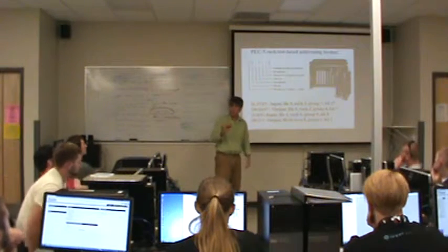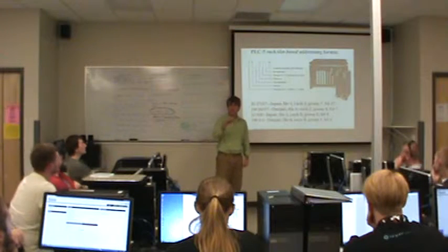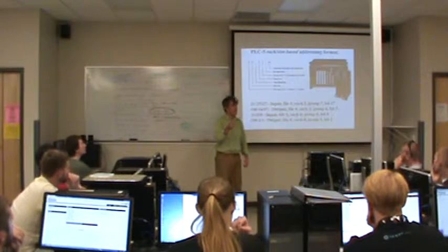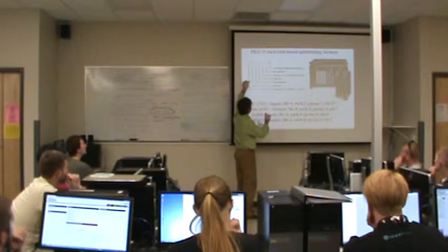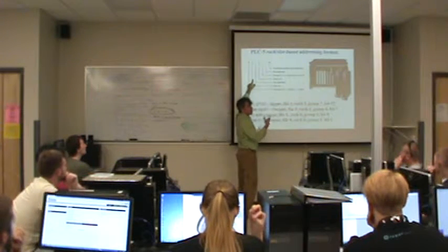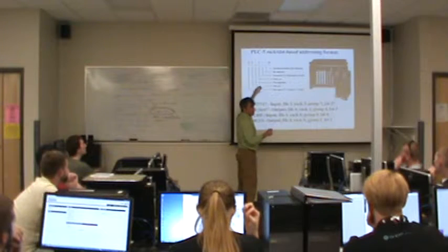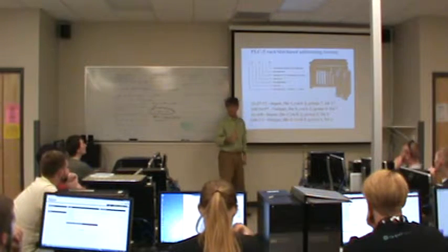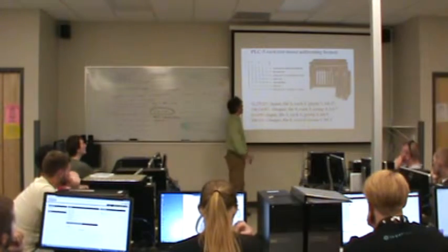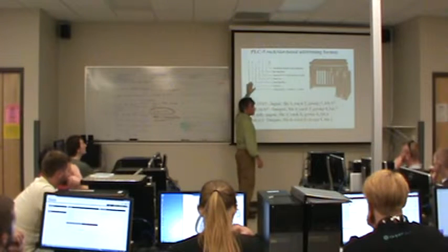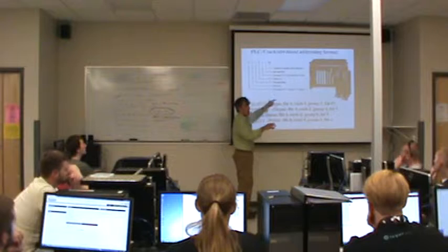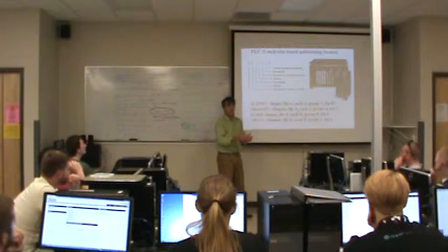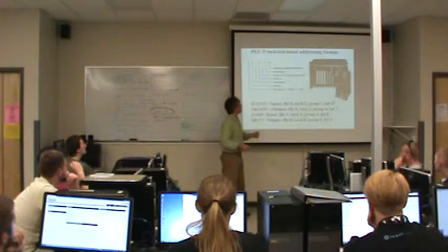Now, when that changes is if you define a file above file 9 as being an input or an output file, then you would need to say I, and then whatever the file number is. For example, I10, you could make an input file, or I11 could be an input file. You'd have to address it that way, because then the two are not redundant. You have another file besides file 0 that's talking about an output, or another file other than file 1 that is an inputs file.